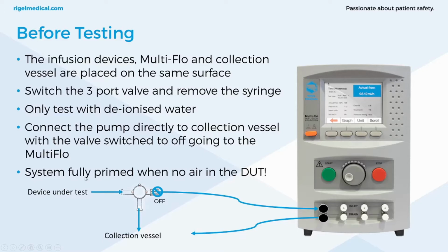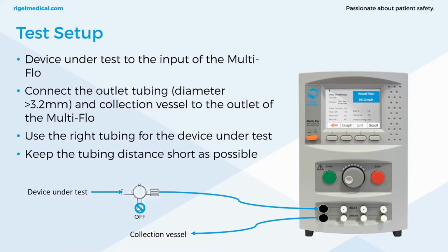So the system is then fully primed with no air in the device under test, so we're going to fully prime that until we're seeing no air within the system. And then with this system, we've cleaned the system using the priming. We've got no air in this part of the system. We should have no air in this part of the system. We should be ready to test. But if there is still a little bit of air within the system, before testing, we select a drain test, which is what we're going to do in the example in the video.